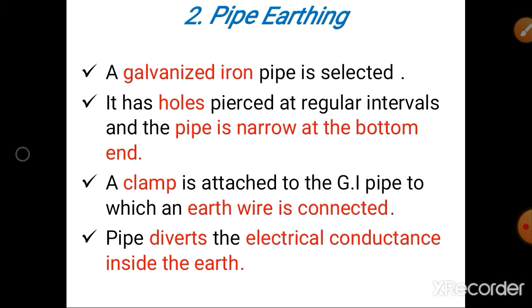Here in the galvanized iron pipe we have holes at regular intervals, the bottom portion is narrow, and at the top we have the clamp. In that clamp we connect the earth wire. With the help of this galvanized iron pipe, we discharge the extra energy, otherwise leakage current, to the earth. In pipe earthing, the pipe is normally placed in the earth pit at a depth not less than 3 meters. After inserting the galvanized iron pipe into the pit, the space inside the GI pipe is normally filled with layers of salt, charcoal and sand, that is, alternate layers of salt, charcoal and river sand up to the clamp level.